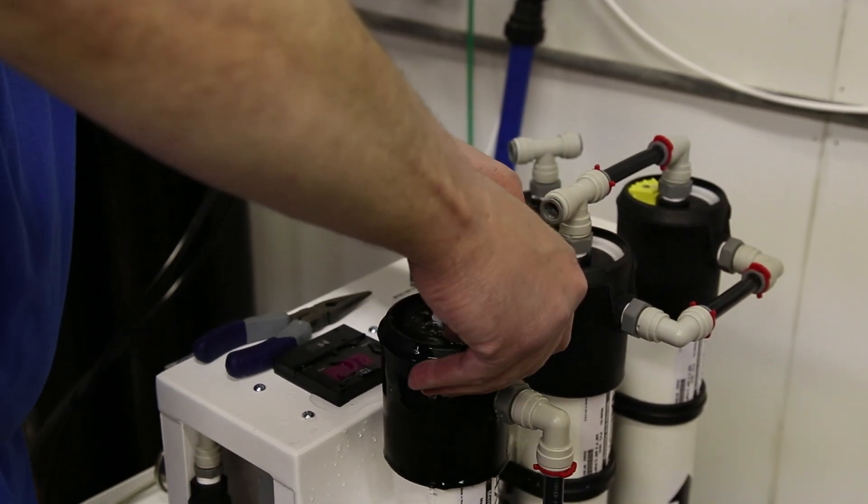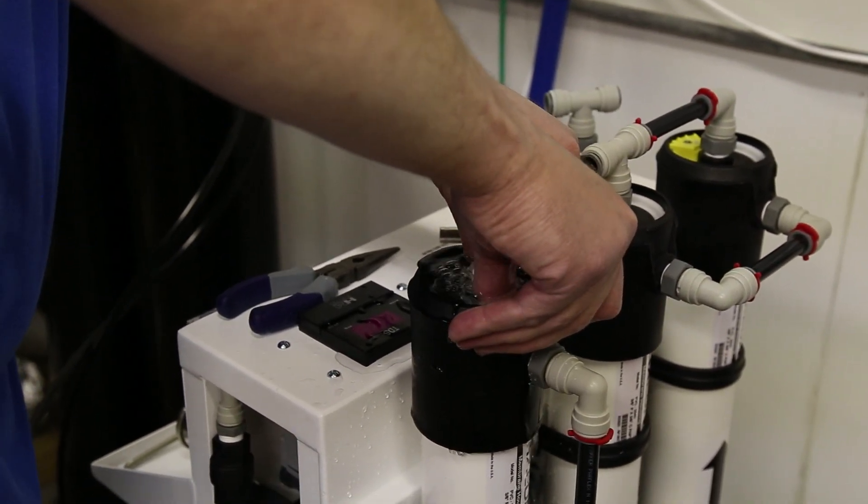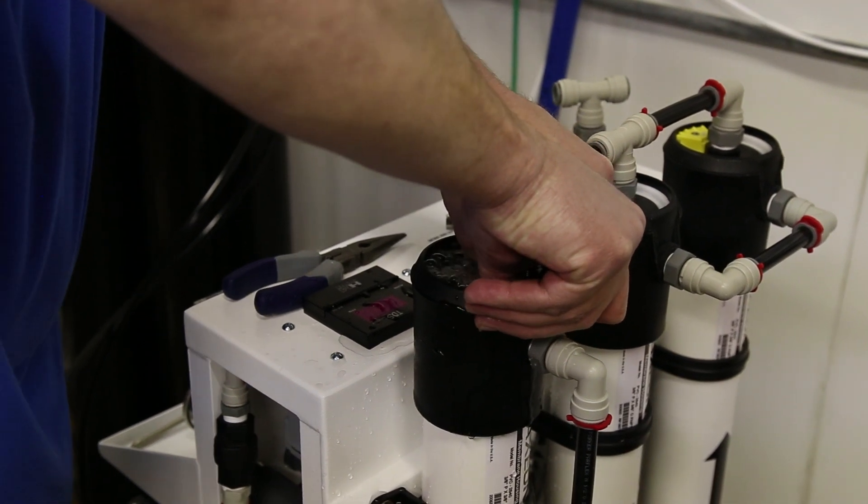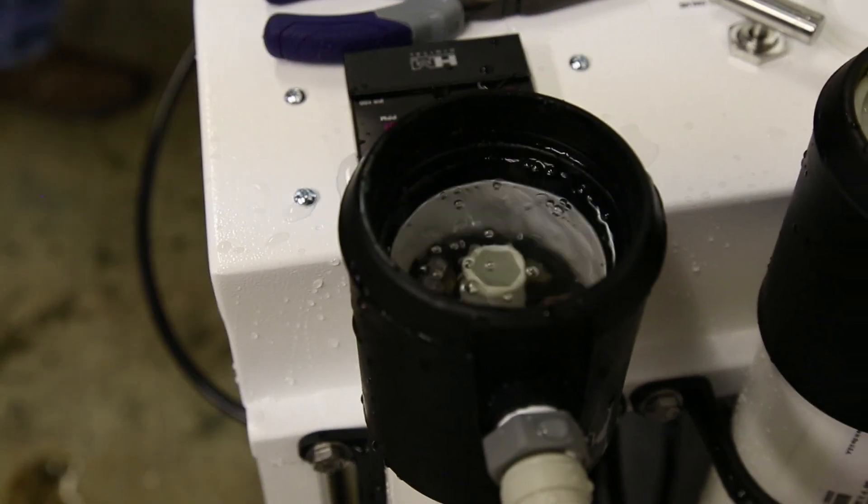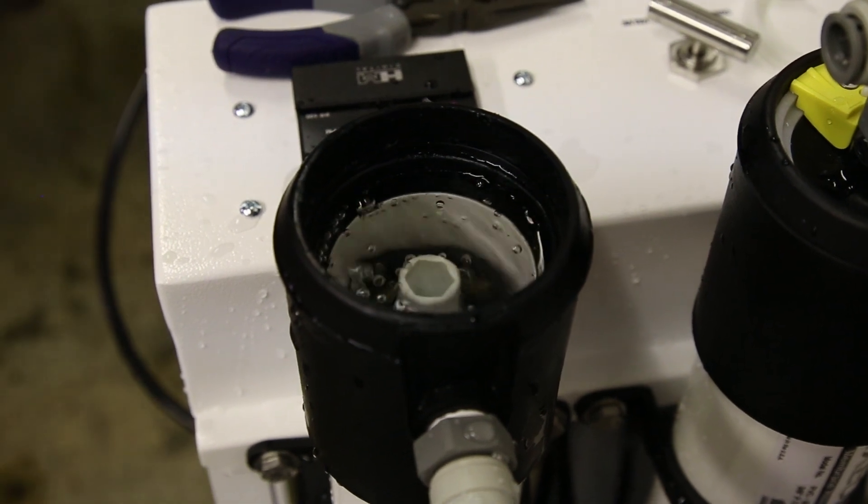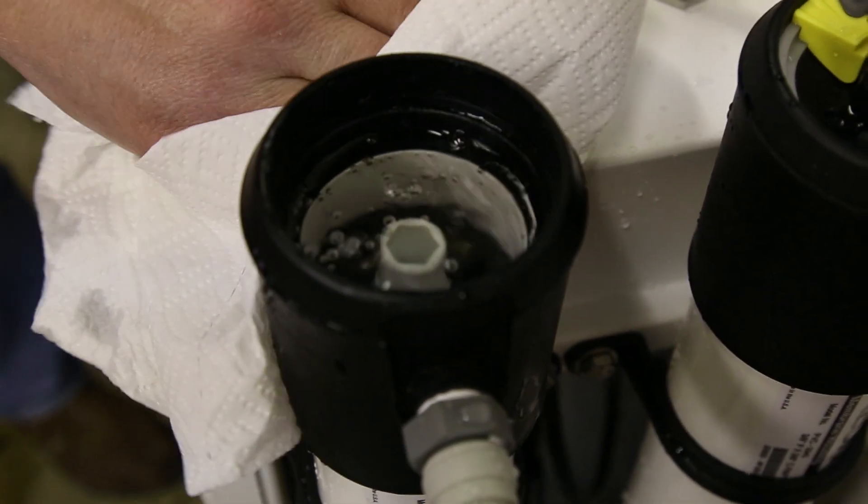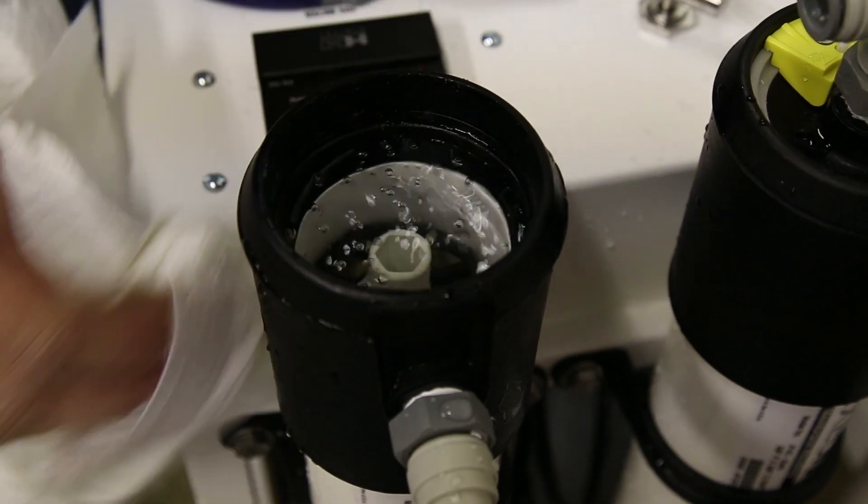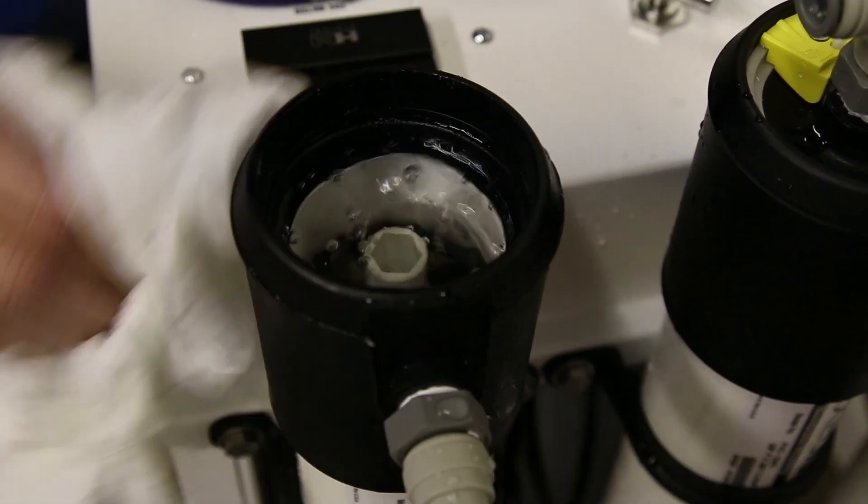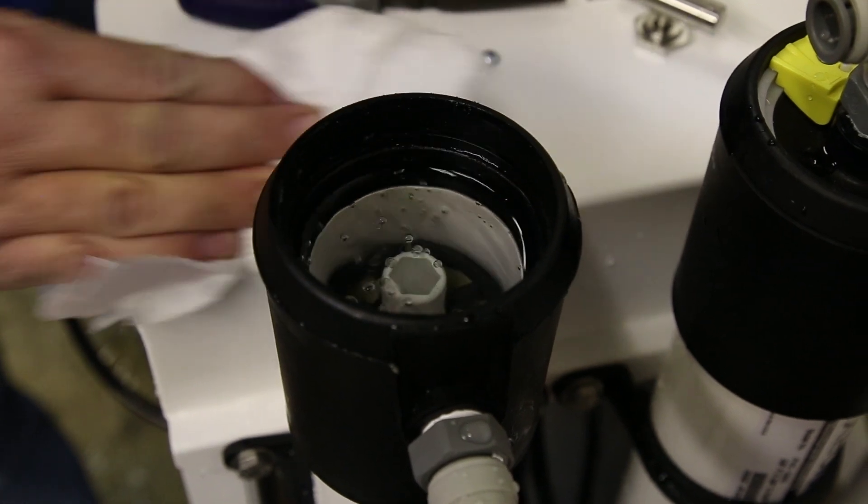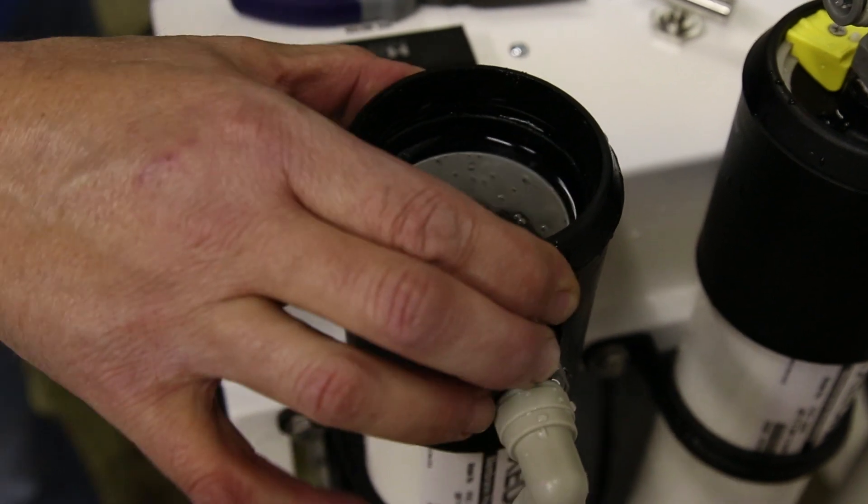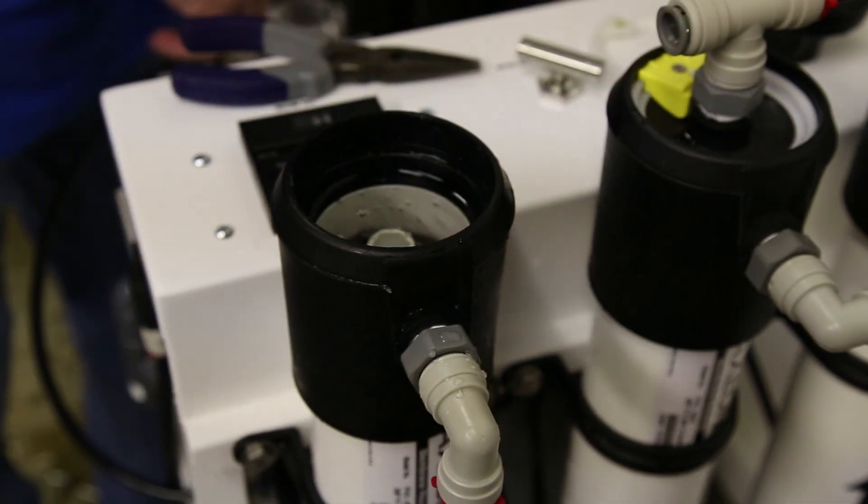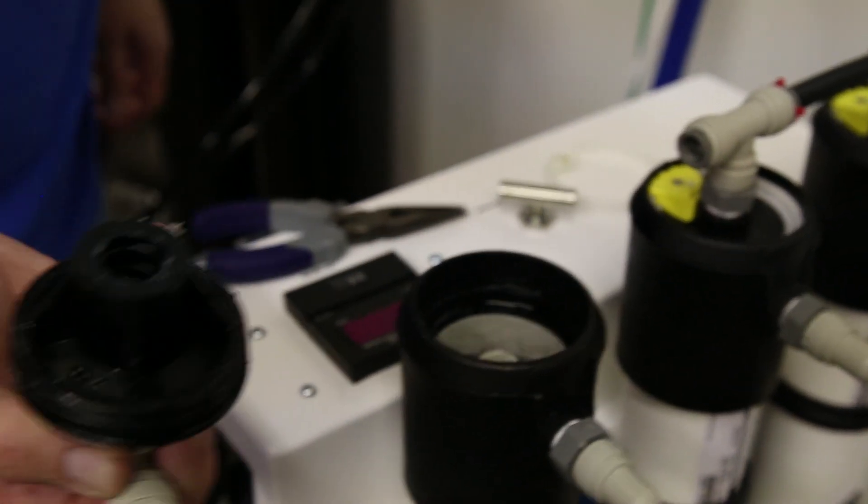Continue to twist it as you let it down through there. That'll ensure it's not rolling the seal. It'll get a little tougher as you get to the bottom because there's a little water in there that'll start forcing through the membrane. The fact that water forces through lets me know that skirt seal is in the right position. We're going to push it all the way down until it's fully seated. You'll actually see some air bubbling up, and that's the air coming back out.